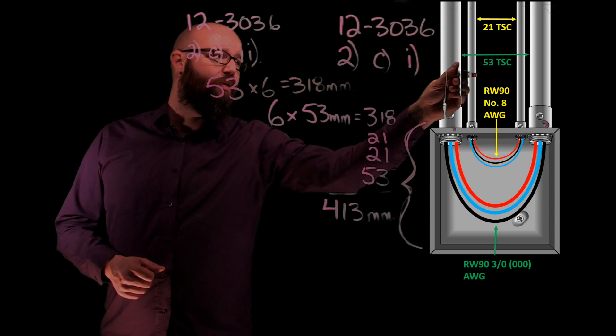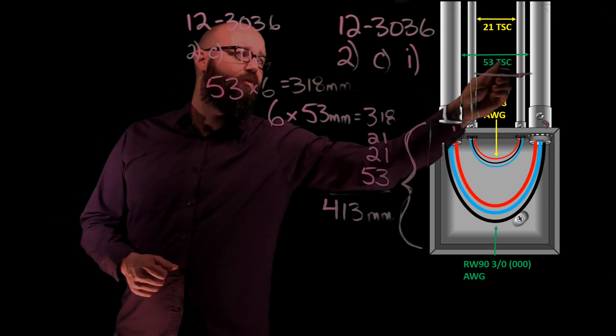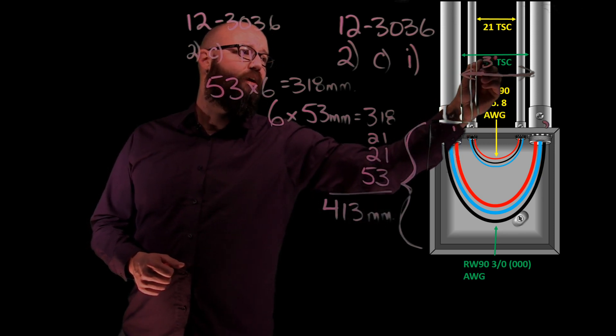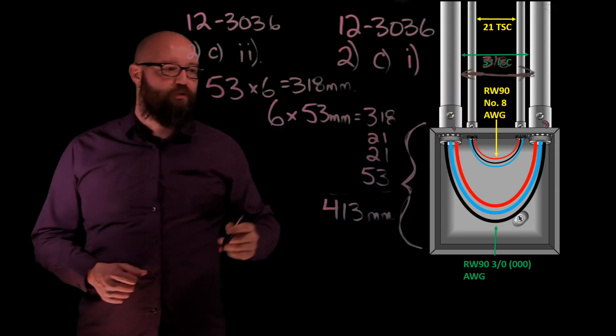I'm going to make sure that in between these two right here, or rather our outside ones are 53 trade size, we have at least 318 millimeters between them.